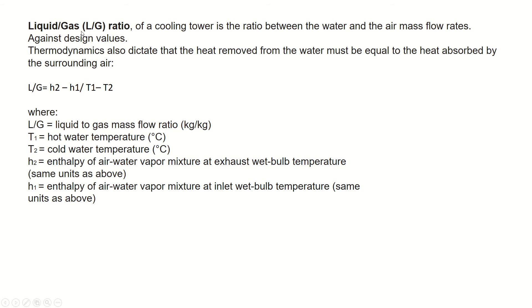The liquid-to-gas ratio, also called L/G ratio, is the ratio between water and air mass flow rates. It equals (H2 minus H1) divided by (T1 minus T2), where T1 is hot water temperature, T2 is cold water temperature, H2 is the enthalpy of the air-water vapor mixture at exhaust wet bulb temperature, and H1 is the enthalpy of the air-water vapor mixture at inlet wet bulb temperature.